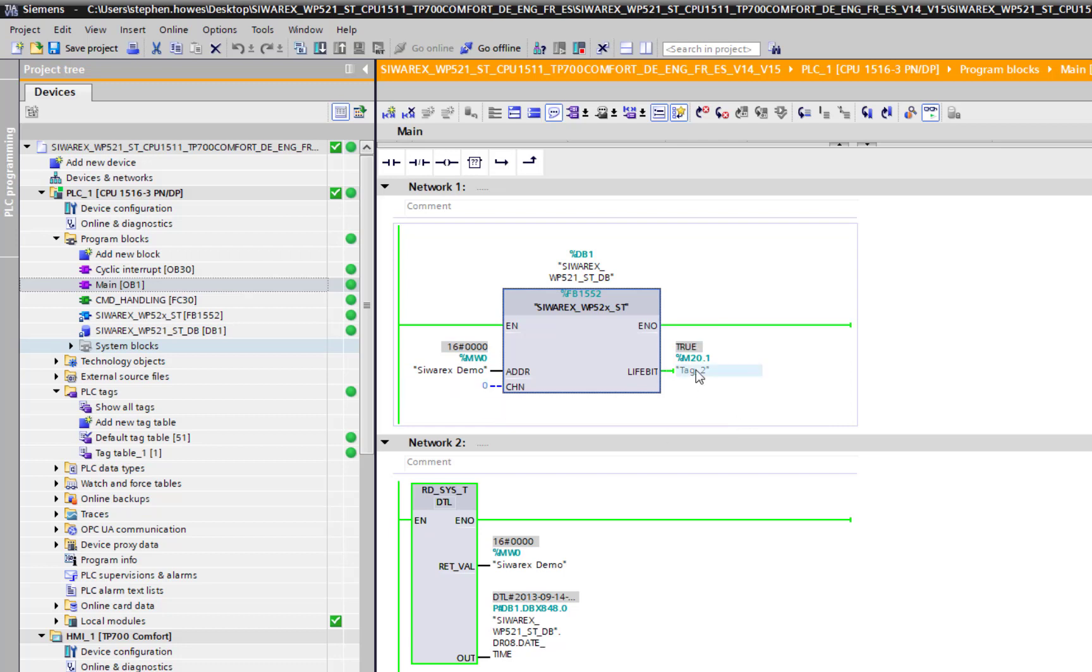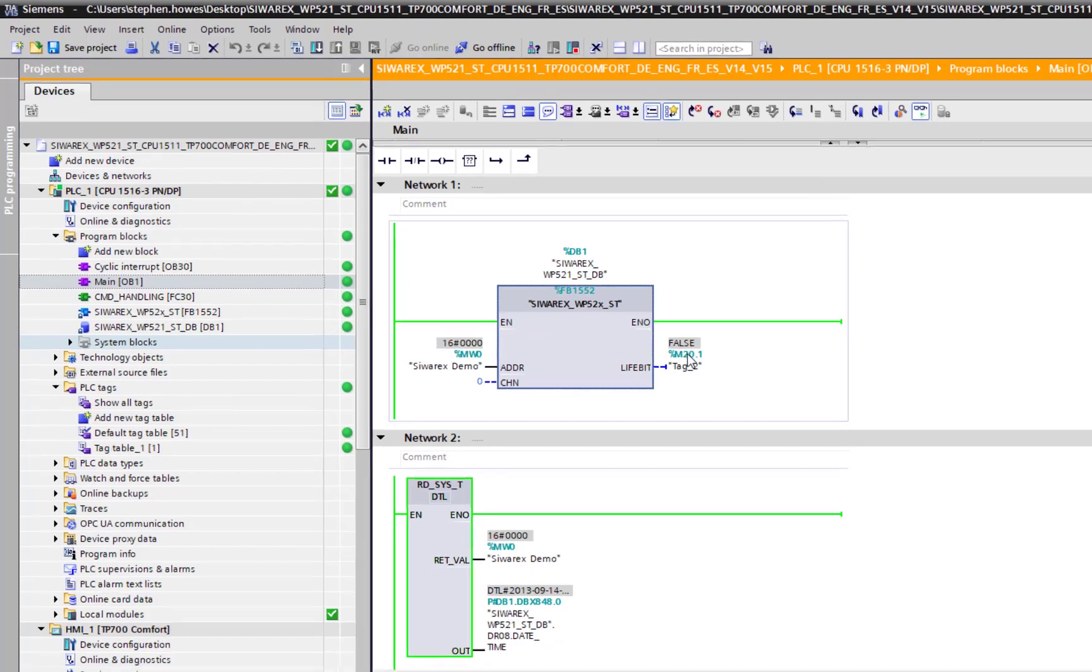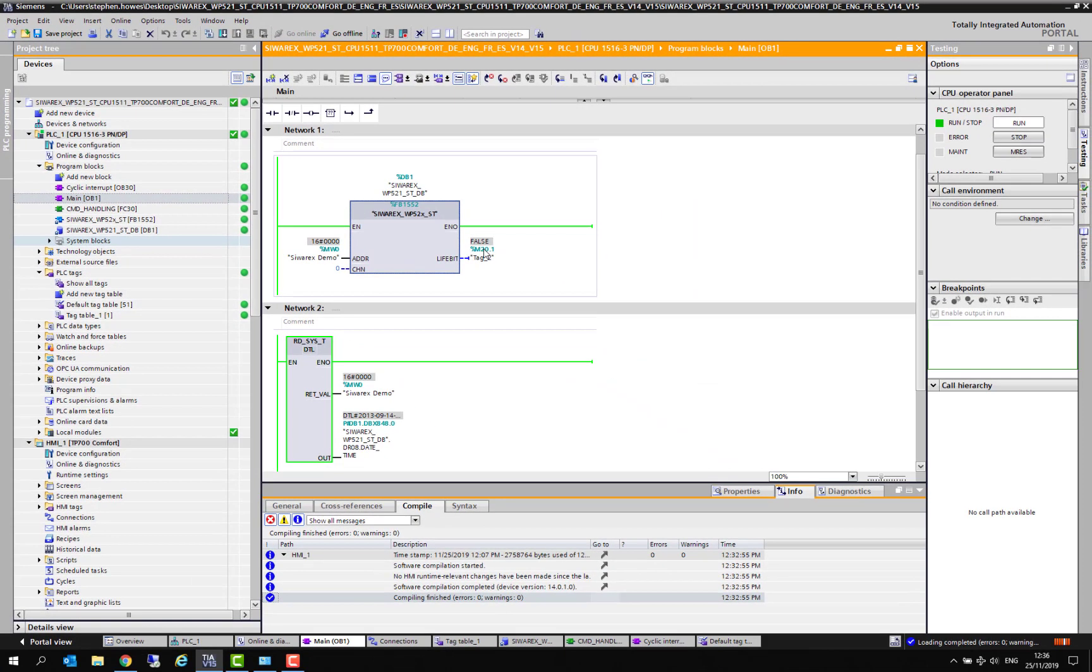Then go to your OB1, set that into the address and then set the channel to zero. It's up to you whether you give it a permanent or a temporary tag just to test it, but make sure that you set the tag for the life bit. Do a compile and download and as soon as you see that true and false flashing we've got communications with the Siwarex. There you go, it's as simple as that.